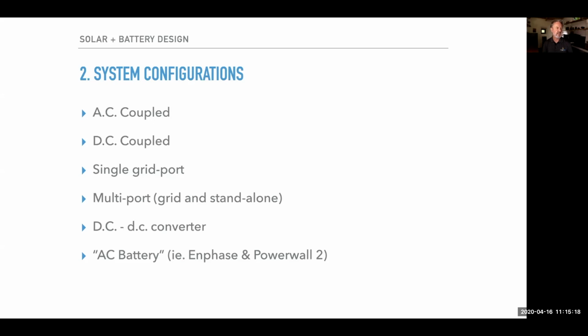Some devices have just a single port. What do I mean by port? I'm using the language of our inverter standard 4777. We refer to inverter ports, like the AC grid port, the communication port, the DC input ports, maybe an AC output port. There are some systems that have a single AC port that can change its nature from being grid following to standalone. I'll give a diagram for that in a second.